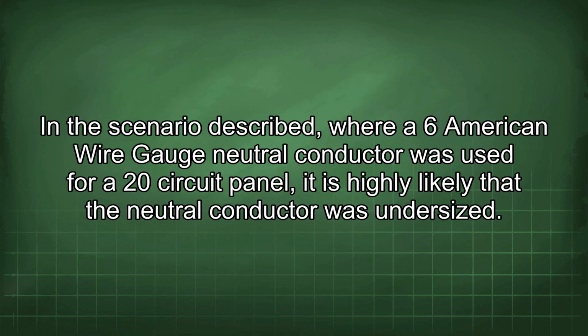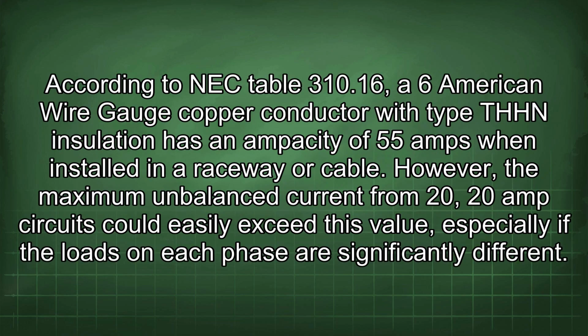In the scenario described, where a 6 American wire gauge neutral conductor was used for a 20-circuit panel, it is highly likely that the neutral conductor was undersized. According to NEC Table 310.16, 6 American wire gauge copper conductor with type THHN insulation has an ampacity of 55 amps when installed in a raceway or cable. However, the maximum unbalanced current from 20, 20 amp circuits could easily exceed this value, especially if the loads on each phase are significantly different.